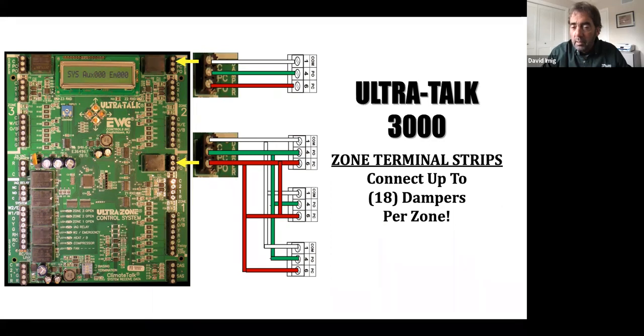Now, if I'm connecting multiple dampers, our suggestion is that you home run more than one time. In fact, we require you to home run more than one time. So don't daisy chain 18 together and bring it back from the last damper. Utilize the ability to get 3 wires into our terminal. Each one of those, the common, power open, power close, will accept 3 18-gauge wires. So that gives you the ability, in multiple damper applications, to home run up to 3 times instead of daisy chaining them all together.